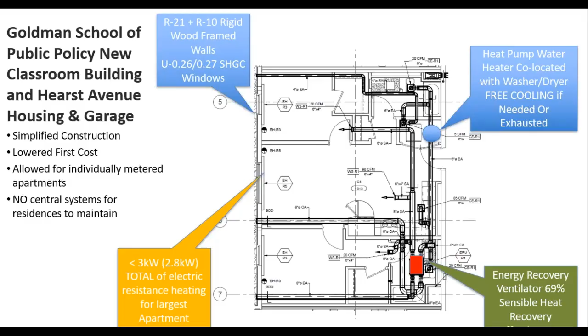At UCSF, we've just been commissioning the Nyle heat pump water heating systems, and this is going to be kind of the model for UC housing projects now for central systems with either Colmac, Nyle, or the other central systems. But operating very well. Heating COP of 4.15 is measured. Measured, Danny? Measured for the system.